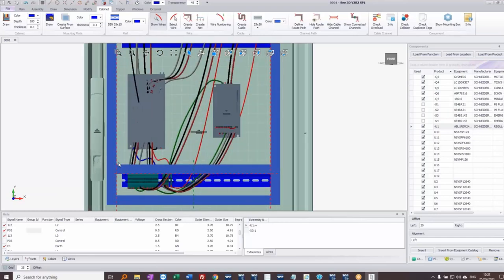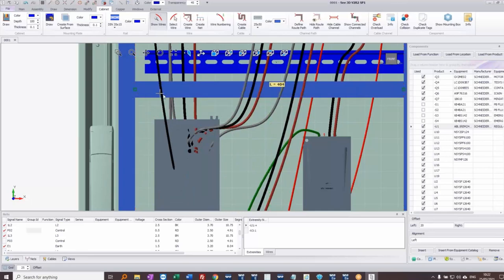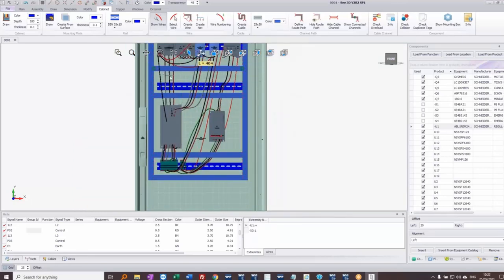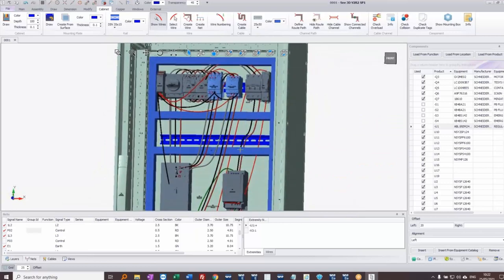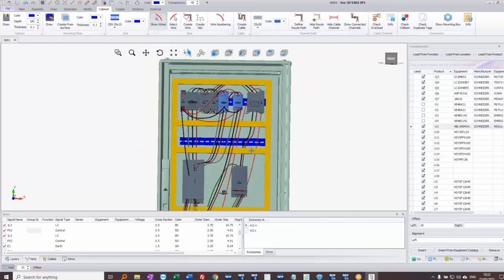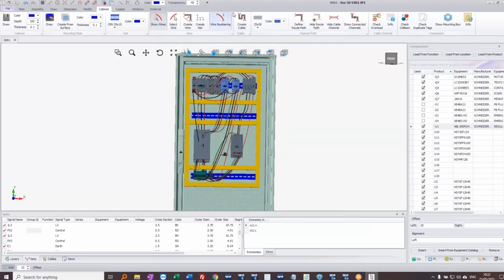I'll zoom in because snapping is on a large grid. On the bottom left you can change the grid — currently 25mm — and you can make it smaller, though zooming in often gives enough control. Once the wireways are placed, I can click 'Show connected channels' to see which are connected together. With them all selected, I can change their transparency — setting it to 45% makes them transparent so I can see devices through them.